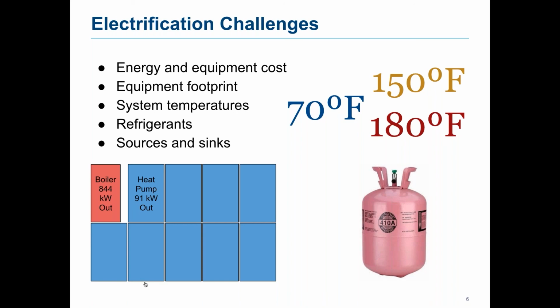Another issue is system temperatures. In existing systems we have target heating temperatures of 150, 160, 180 degrees Fahrenheit. These are achievable with some heat pumps, but typically they come with a penalty to efficiency. So it's probably best to try to operate our systems at lower heating temperatures, which means potentially having to replace coils or make other changes to the existing systems.